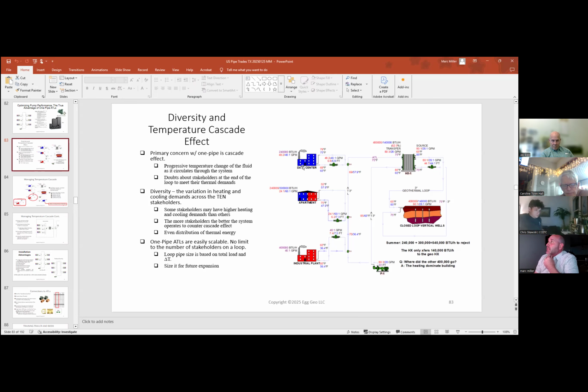We've got a data center. A data center is cooling dominant, meaning that it's always putting heat onto the loop, which for this example is the equivalent of 10 tons. Then we have an apartment building, which has mixed use, a generally even use of heating and cooling BTUs. And then we have a heat dominant consumer or stakeholder on the loop, which is, let's say, an industrial plant that needs high temperature processed water, which is consuming 400,000 BTUs. So all on the same loop, you've got somebody who's cooling dominant, somebody who's trying to heat all the time, being heating dominant, and then somebody that switches back and forth all the time, all right?